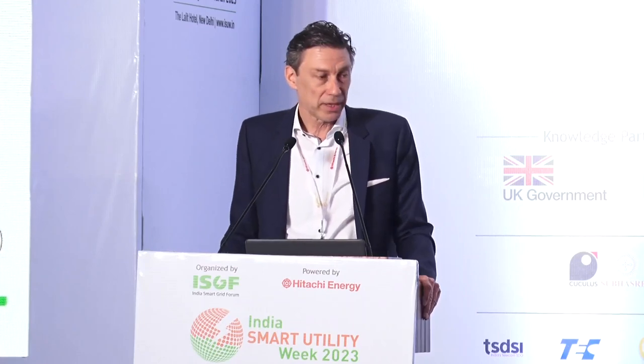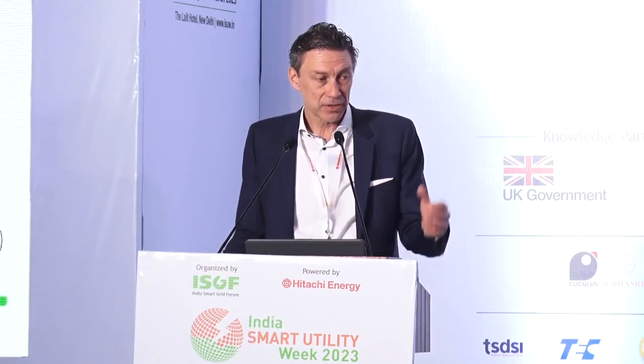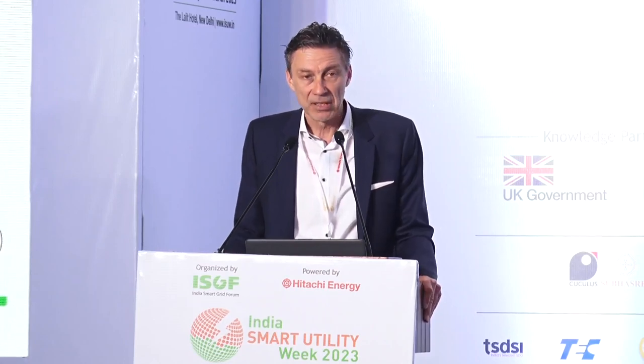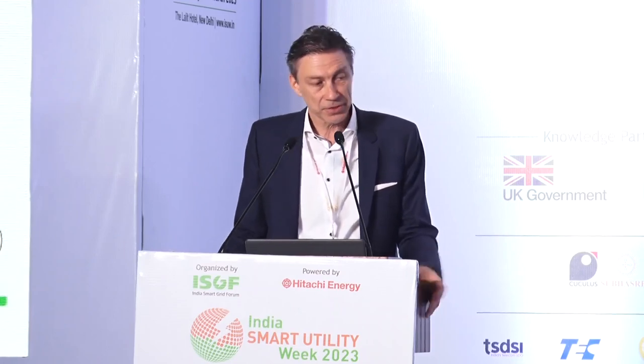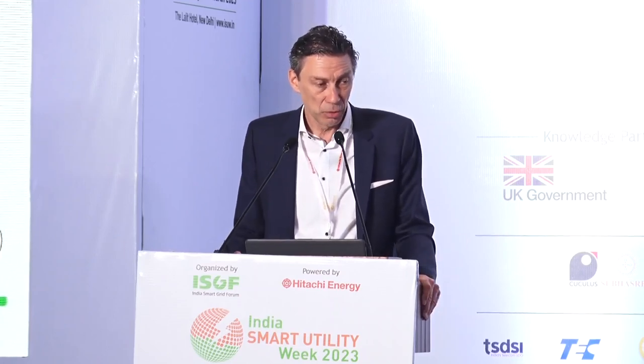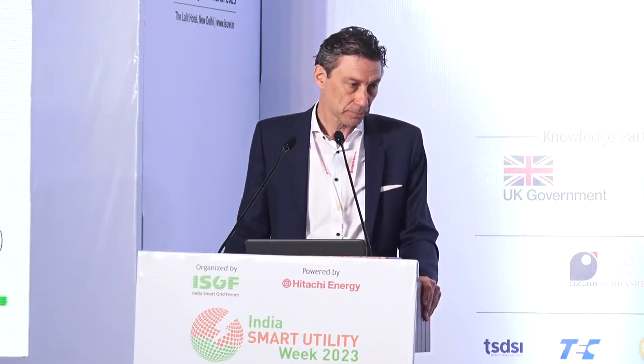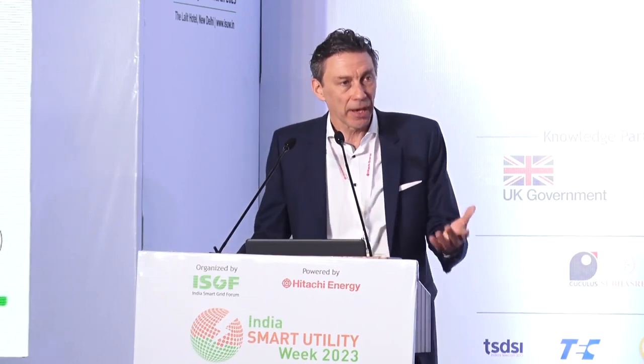This is one example of the results: the failure rates in different voltage classes for different applications of transformers. The most important are the blue bars, the transmission substation transformers. You can see an average failure rate of about 0.5% per year. If you have such a low failure rate, it shows that the design, maintenance, and operation of your transformers are in good condition.